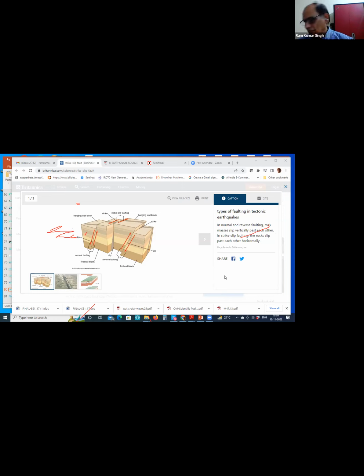So this is one part. Then I also have some official information that the designers overruled the people who gave them suggestions, basically the seismologists and the geologists. They gave some warning that yes, this place is vulnerable because of tsunami considerations, but they overruled that, and perhaps the plant grade height or the design basis flood was not accommodated properly. So this is what I know from official records.